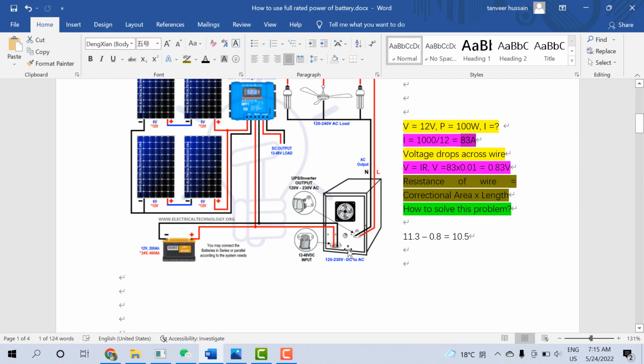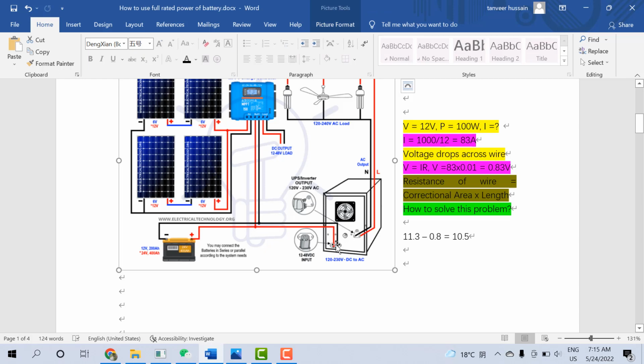What you need to do is connect one time, measure the voltage at this point, plus of your meter here and minus with the black wire here, and for example if you get like 13, then measure on the battery when the load is running. Make sure the load is more than 70%, then measure on the battery again, and find the difference between the two voltages. That would be the voltage drop.